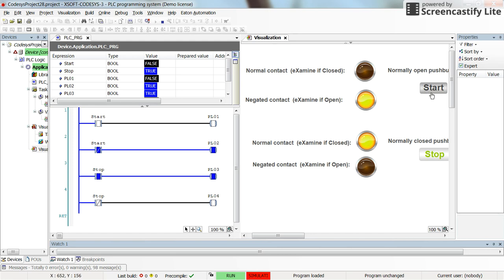Since start is a normally open push button, whenever I don't press it, it's open by default. So the logic for examine-if-open is true, and you can see that the negated contact gives us a true value and the corresponding pilot lamp is turned on. At the same time, the normal contact or examine-if-closed gives us a false value, which is correct because I haven't pressed the start push button — the contact is open, not closed.